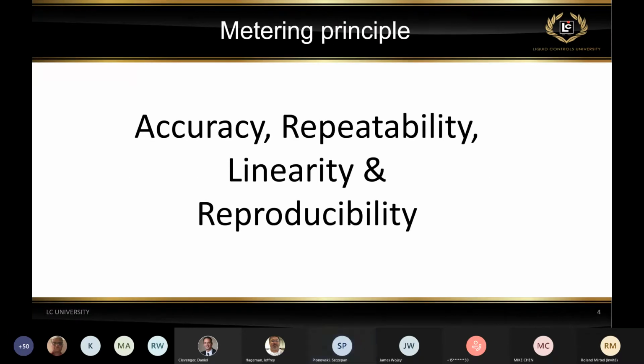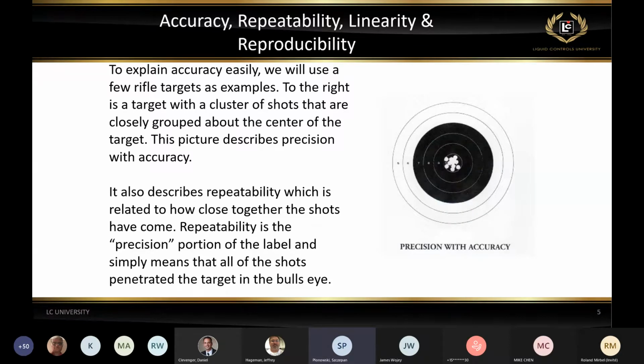But before we get to actual calibration, let's take a look at the basic definitions and basic characteristics of the meter, which is accuracy, repeatability, linearity, and reproducibility. These are the parameters you're going to be really looking at when you're calibrating a meter. One of the easier ways of explaining those concepts is using the concept of a target. If you look at a target, either you're shooting a rifle or shooting a bow and arrow or throwing darts, the concept will be exactly the same.